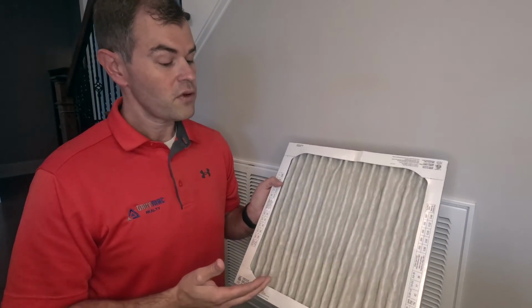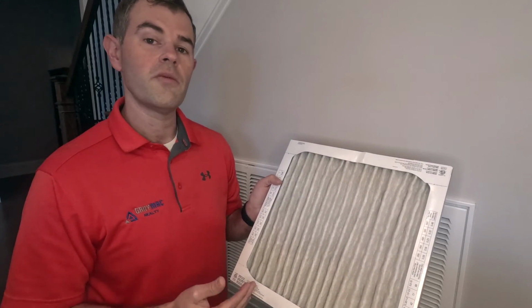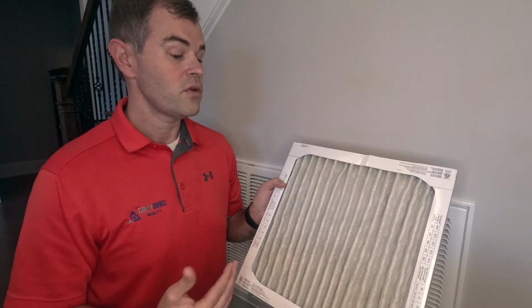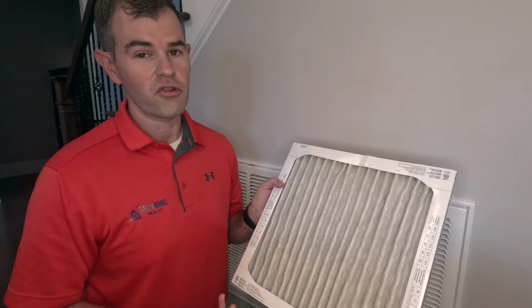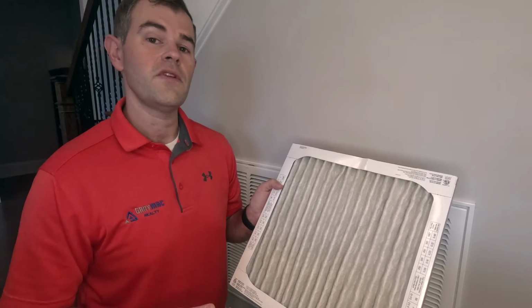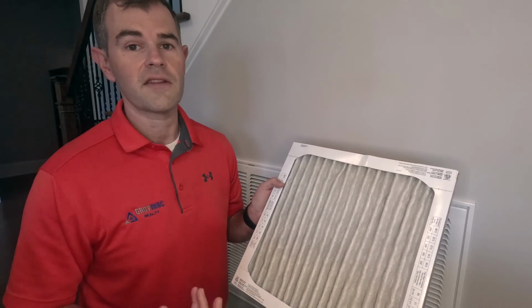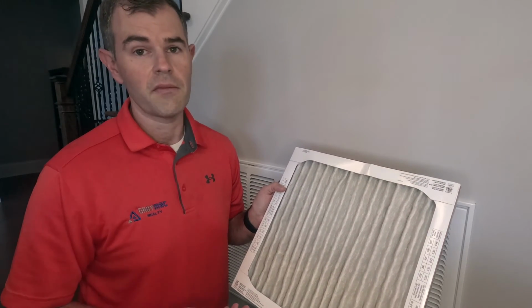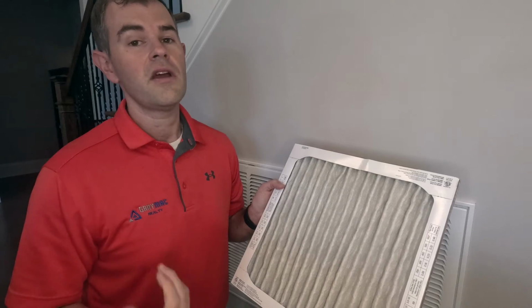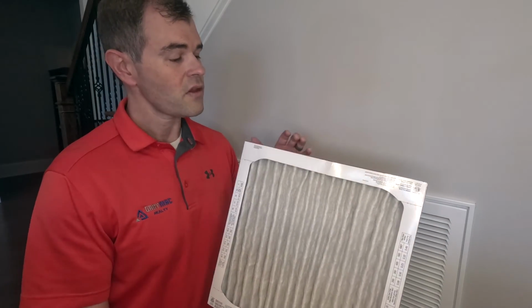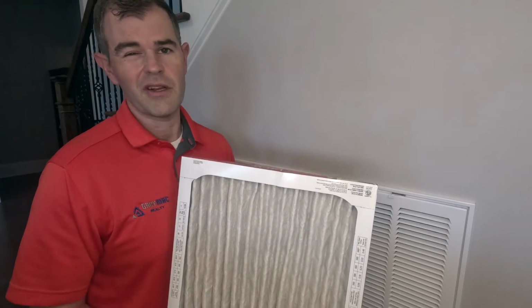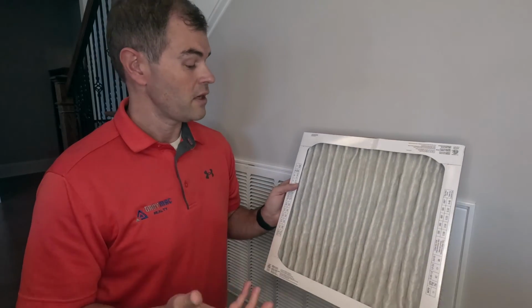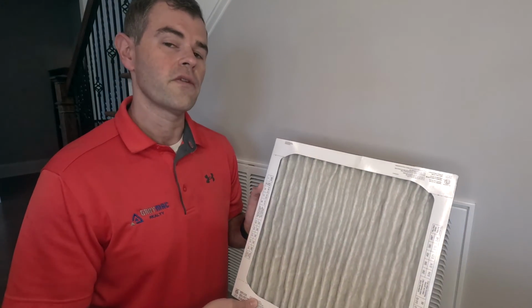So look at the filters, think about what you need for your home and your family. If you can go up to MERV 13, there is a larger pressure drop across those filters. But if you need something that helps filter out smoke and things like that, then a MERV 13 is going to be a little bit better option for you, but you want to change those out about once a month. So it's going to cost you a lot more. You're going to have to change those out a lot more. So these MERV 11s, like I said, I typically change these out about every 3 months. And then it tends to do pretty well for our house.